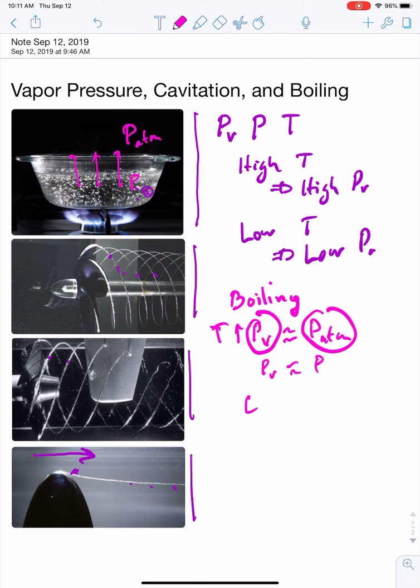What's happening in cavitation, this temperature here just may be, you know, typical room temperature, say 20 degrees Celsius. So if we've got typical room temperature liquid here, then the vapor pressure is actually going to be pretty small. So in order for this vapor to form inside the liquid, what has to happen is that the fluid pressure has to get really really low.